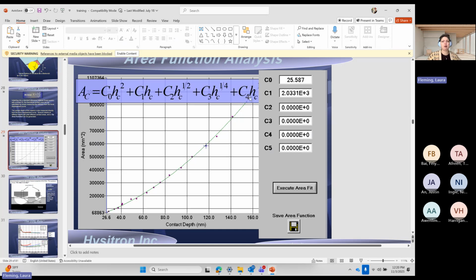However, for most customers, we're trying to make a tip area function that can function well over a range. We want to make sure to not over-constrain it so that C naught can lead to that 24.5 at deeper depths. And then at shallower depths, we have the information that we need to have an accurate tip area function, even though it's not acting like an ideal Berkovich probe.